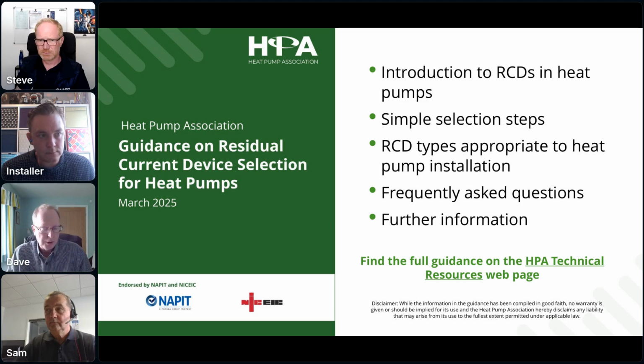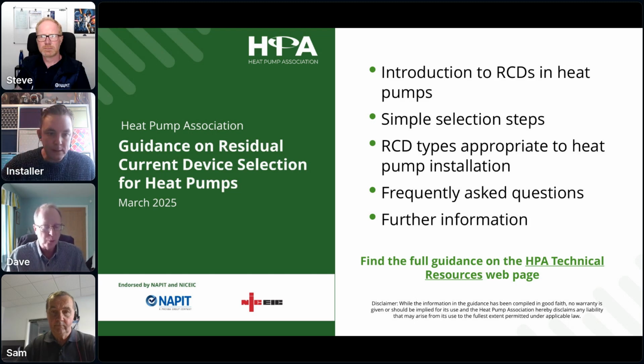Yeah, so I'm picking up on the comments from Steve and Sam there. Safety, the way that the RCD works, and whether it results in protection for consumers and individuals. The correct selection is important, and the reason for that is that most heat pumps, not all, but most heat pumps will have components that will produce different situations in terms of earth leakage. So frequency components different from the 50 hertz that we're used to in the normal supply, direct current components, all mixed up in a signal, and therefore picking an RCD that will actually work correctly is really important.